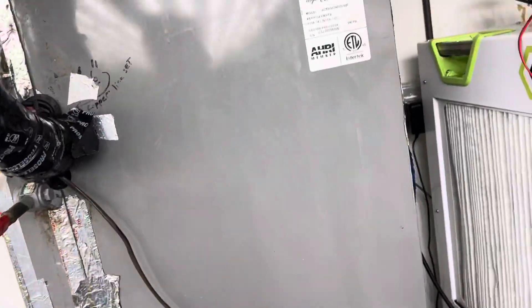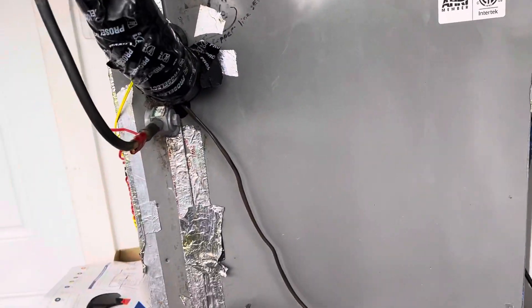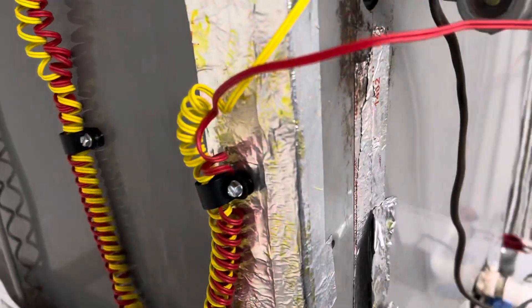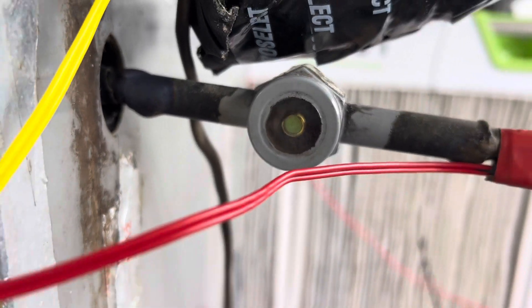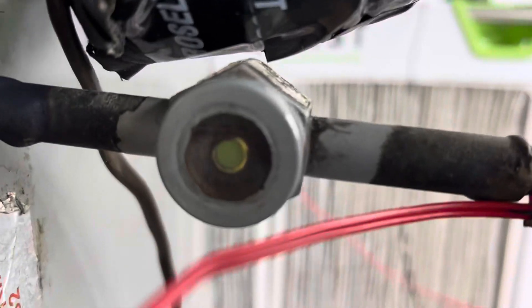Since I know I leak checked this and the one part I had hardest access to was this evaporator, I am going to be tearing open this evaporator panel and double checking the evaporator again. Because I had this rat's ass right on the money working perfectly, so I missed the leak. I know I missed the leak.